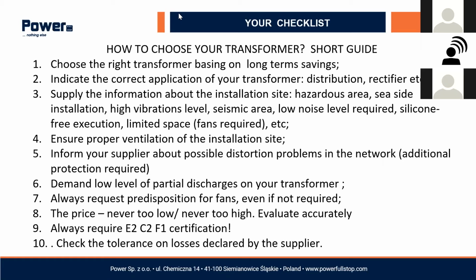fans. We saw that many manufacturers, especially Italian ones, if you do not declare from the beginning that in the future you want to install the fans, will reduce the height of the transformer, and the lower yoke will be reduced, the installation level will be reduced. In that case, you have no possibility to install the fans later, and maybe you will need them. So when you are placing your order, this is our first advice: please always write that you need the predisposition for future fan installation.